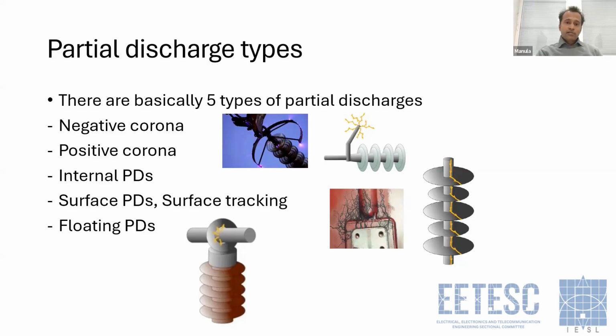And the next type is surface partial discharges. As you can see in these two pictures, it can happen along the surface of high voltage insulators, most of the time because of contamination of these insulators. The contamination can happen due to dust and salt, together with moisture. Those create localized partial discharges, and they can be easily detected with acoustic cameras because they are happening externally. Over time, these surface discharges might cause permanent damage, so-called surface tracking. Like in this picture, you can see these carbonized paths. Those are called surface tracking. And if you don't take action, even at this level, it might lead to a complete flashover and failure of the equipment.